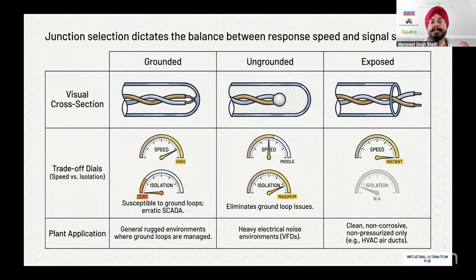what is going to happen is the isolation breaks. You will not be able to get proper temperature, and you must have seen the temperature sensors fluctuating too high sometimes on the SCADA. So the grounded one should be used primarily on good applications. Good application means the application in the process where you can have better grounding and all those things, you can just use that.